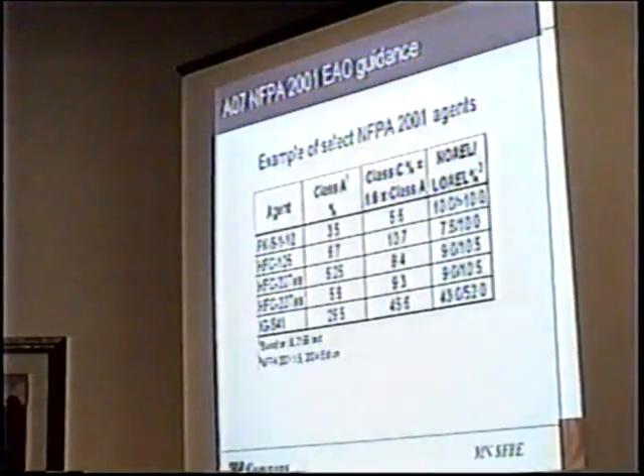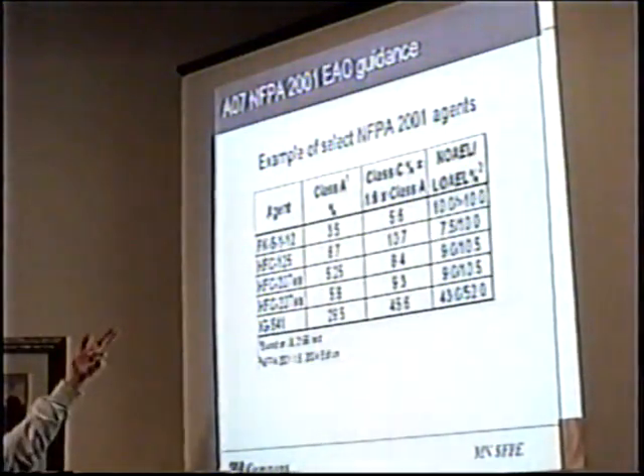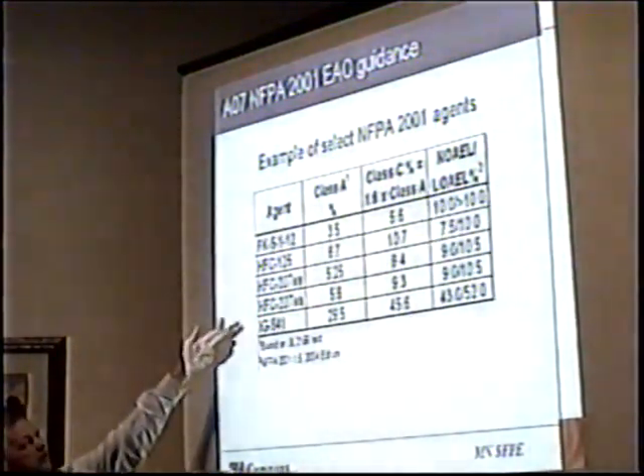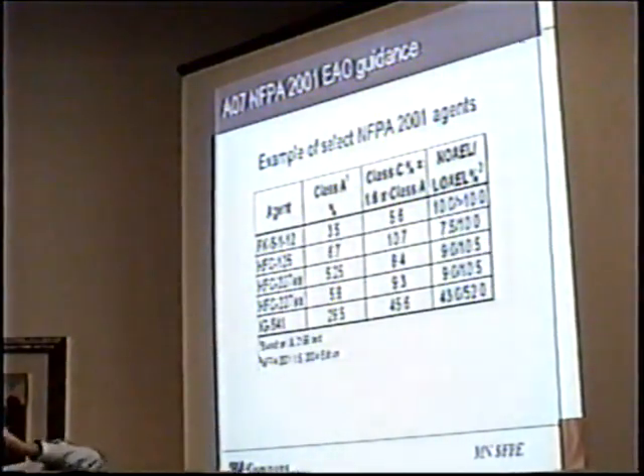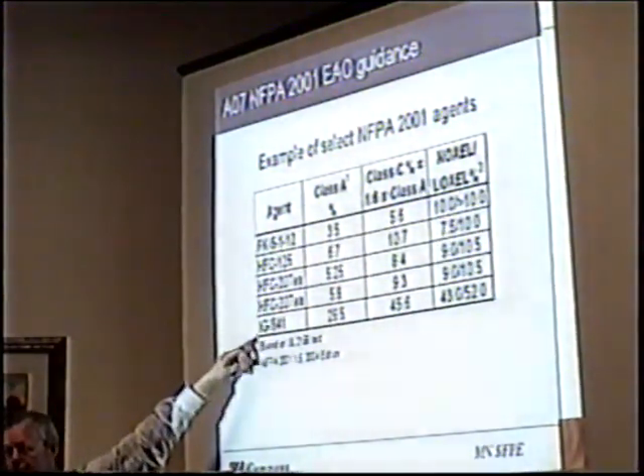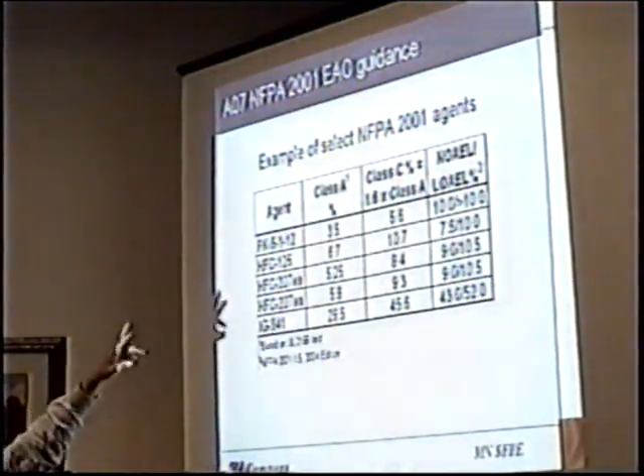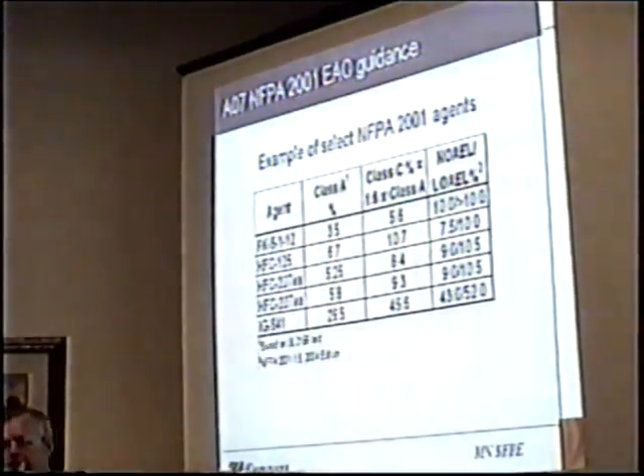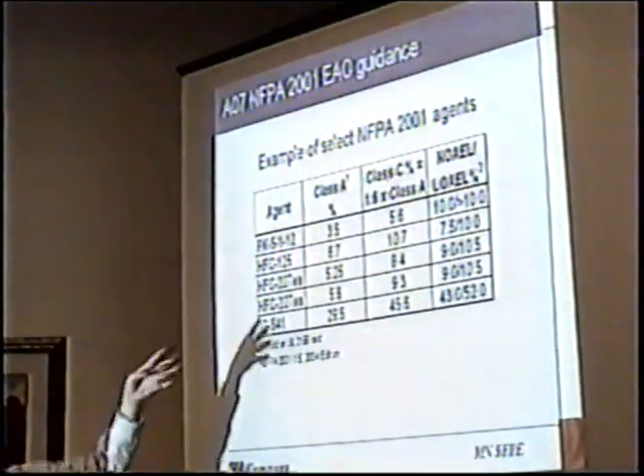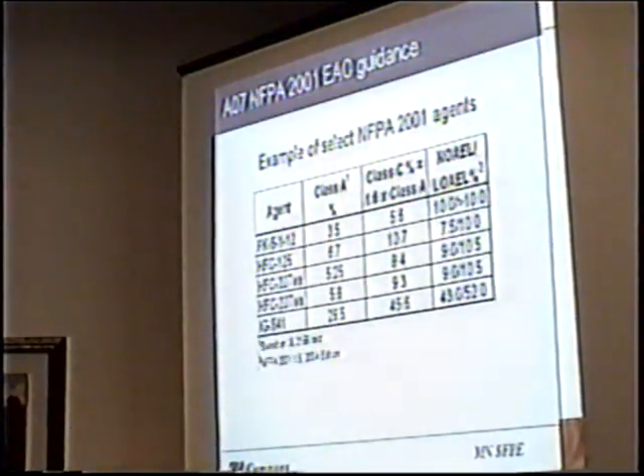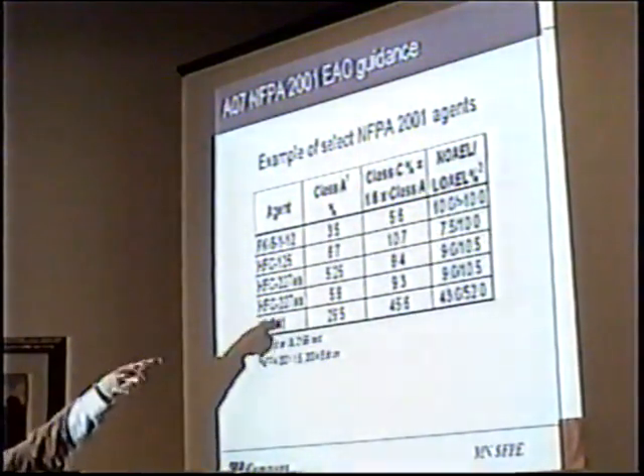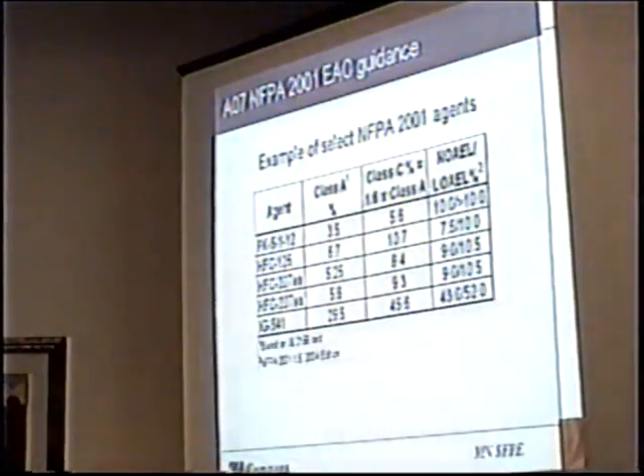An example of the selected NFPA 2001 agents: you see FK 5-1-12, HFC-125, HFC-227ea, a couple of concentrations through HFC-23, and inert gas IG-541. You can see the Class A extinguishing concentrations from the UL testing for those particular agents for those scenarios, and then 1.6 times that for the Class C design. Compare that with the no observed adverse effect level, and you can see why some people may be a little bit upset or concerned about it.